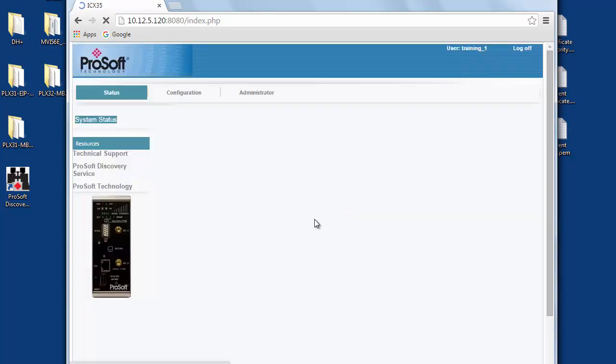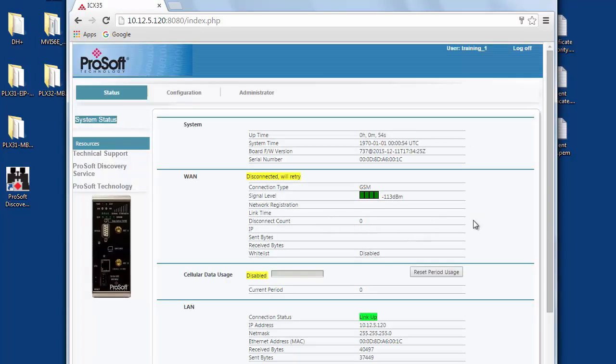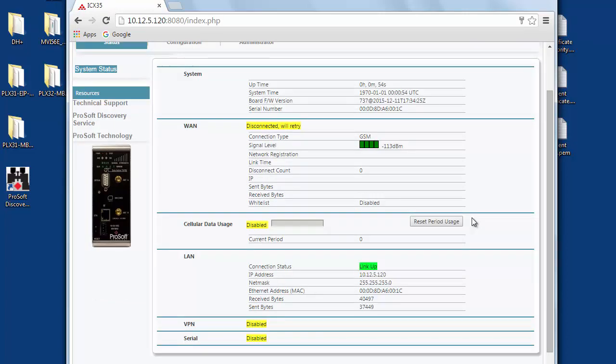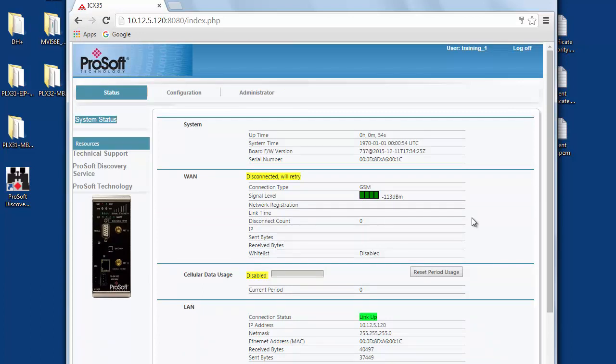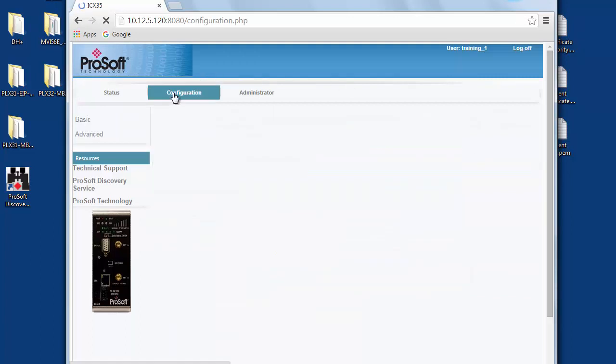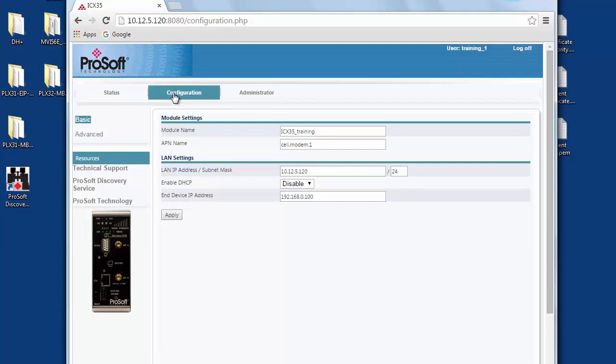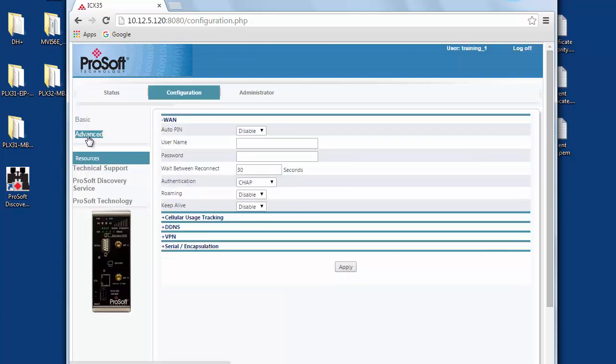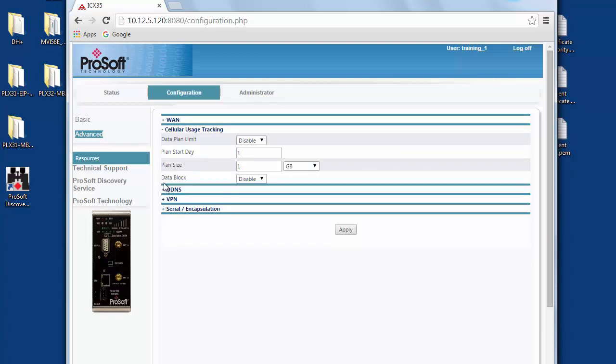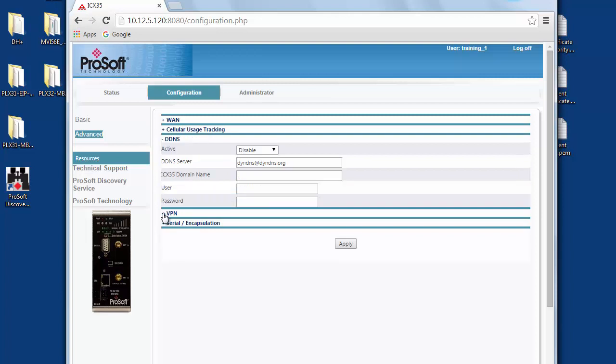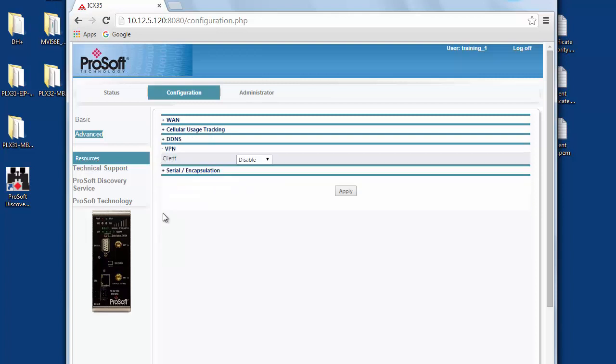Now we can configure the modem to suit our application which is to allow pump jacks in the field to communicate with a SCADA system using our OpenVPN server. For this we will need an existing OpenVPN server waiting for client connections. We'll be configuring this radio as a client connecting to the OpenVPN tunnel. Under the configuration tab we'll select the advanced page on the left. Here we can see and configure all the features and functionality that the ICX-35 has to offer. Each of these sections can be expanded to get at the configuration options. We'll expand VPN and in the drop down menu we'll select OpenVPN.